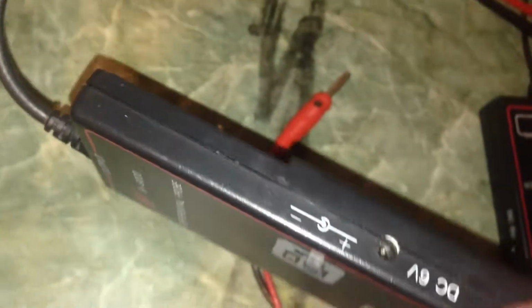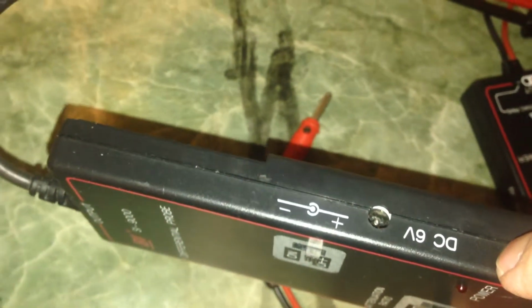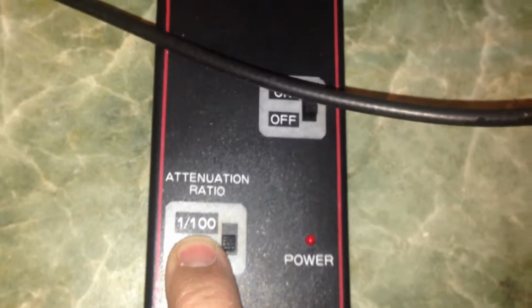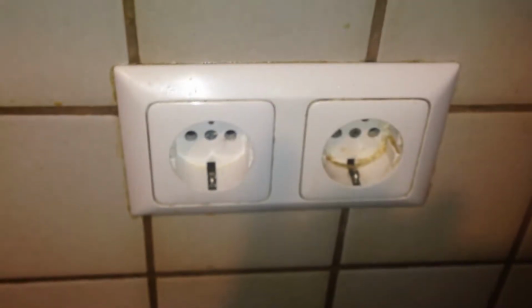And also it needs four batteries, and also it's able to connect to the DC adapter to use it by DC adapter, but I highly recommend to use the battery because when we are going to use a different AC source, it is much better to use a battery. So I will close the battery door. So I have two options, 1 divide 10 and 1 divide 100. It's dependent on the power source, for example 110 or 220 may show on your oscilloscope scale higher, then you can change it to have it without changing the scale.